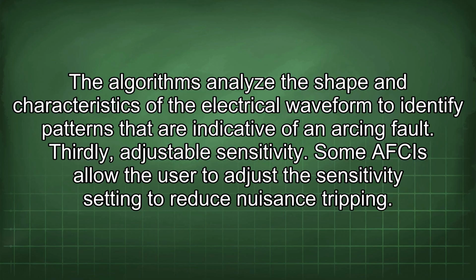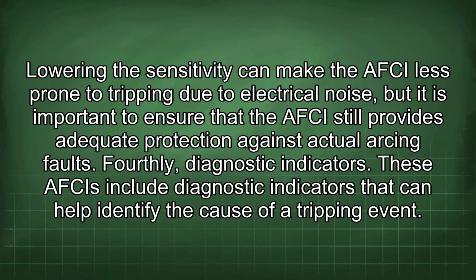The algorithms analyze the shape and characteristics of the electrical waveform to identify patterns that are indicative of an arcing fault. Thirdly, adjustable sensitivity. Some AFCIs allow the user to adjust the sensitivity setting to reduce nuisance tripping. Lowering the sensitivity can make the AFCI less prone to tripping due to electrical noise, but it is important to ensure that the AFCI still provides adequate protection against actual arcing faults.